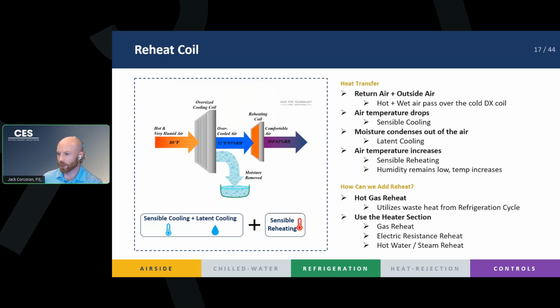And we have a couple different ways we can achieve the reheat. The most economical way to do it in a packaged rooftop unit is with hot gas reheat. This is great because it just uses the waste heat in the refrigeration cycle. It just has another coil downstream. Our compressor is just going to send the hot gas to a reheat coil, and that allows us to get a little bit of sensible heating without having an entirely separate heating section, right? We could use gas reheat, or we could use electric reheat, or hot water or steam, but as we said, if we don't have to use that energy, we already have it from our DX coil for overcooling the air. Why not just run a little bit of hot gas back a little bit downstream, and that way we save energy, and we also get the reheat and dehumidification that we need. So this is a very powerful tool when you have high latent loads or high humidity that you want to get rid of.